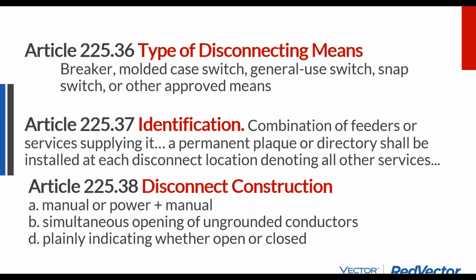We get into simultaneous opening of ungrounded conductors. So it's not a disconnect switch for each pole. It's a double pole disconnect switch where the one switch disconnects both poles. In the boat marina industry, you might get single pole battery disconnect switches for turning the battery off so the battery doesn't drain when you're not using the boat. That's not the same disconnect switch that you can use for disconnecting these power feeders. Plainly indicating whether open or closed.